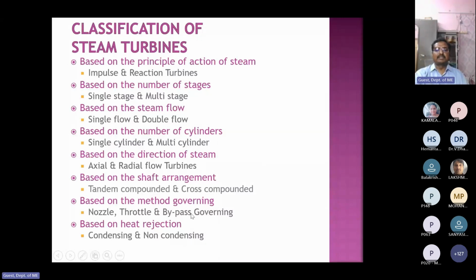Bypass governing is used in combination with nozzle and throttle governing. It attaches to the first stage or second stage. For example, if you quickly increase the load, the bypass governing valve opens and supplies steam directly at the second stage and quickly raises the load.